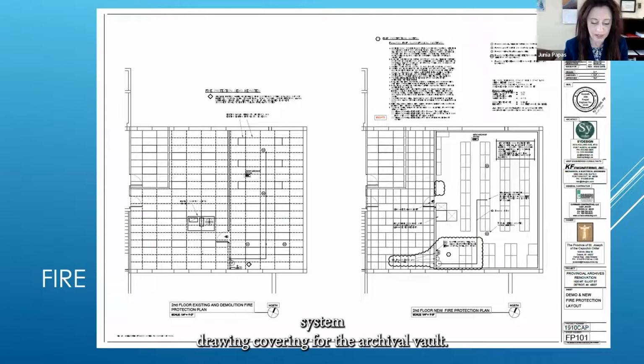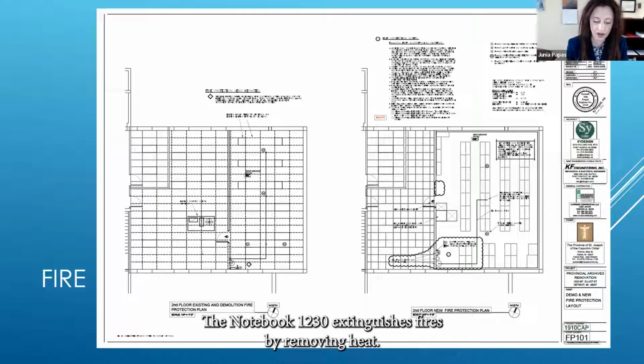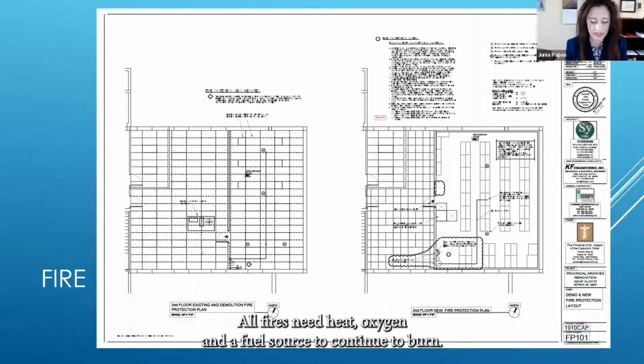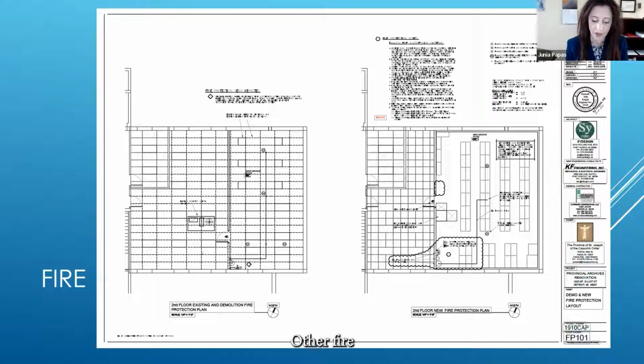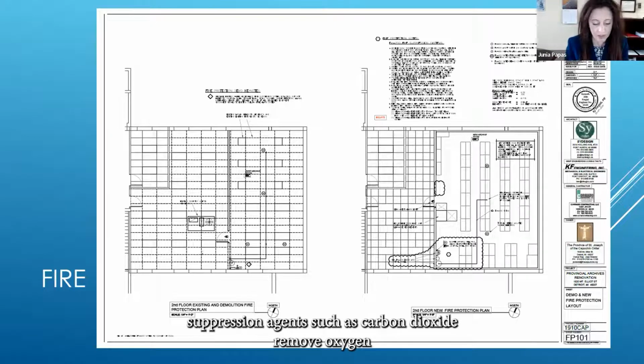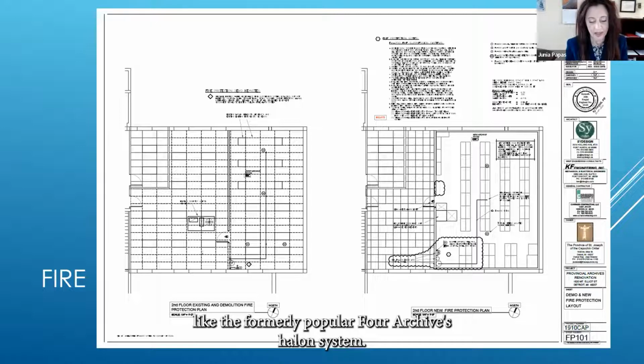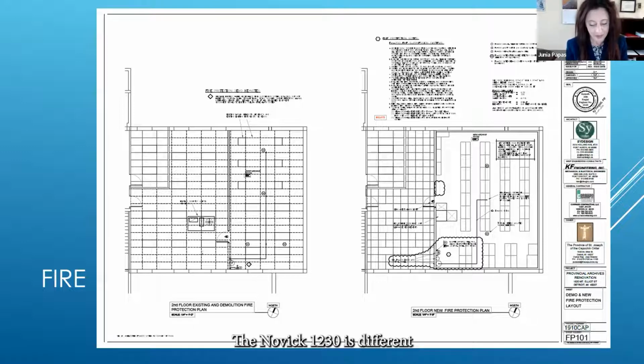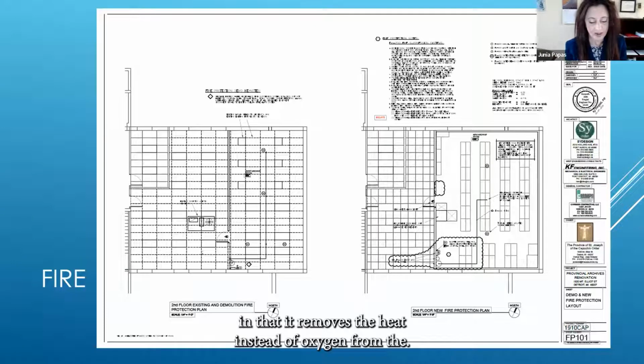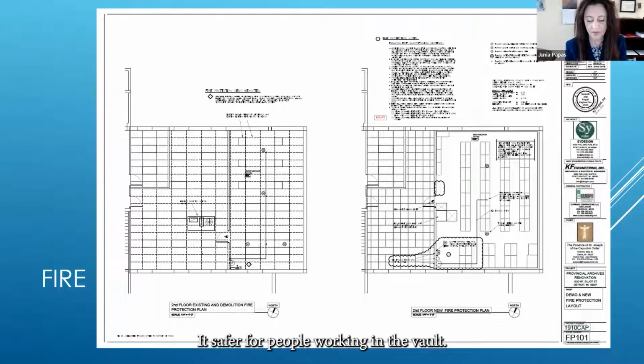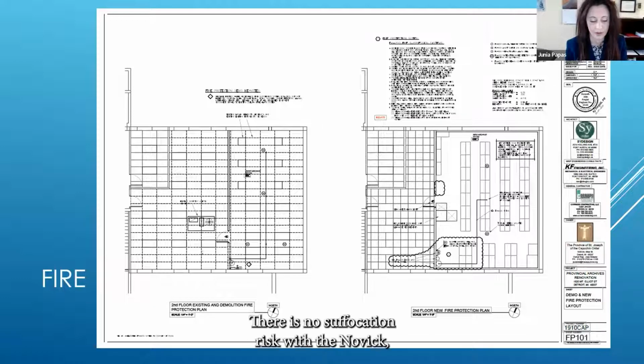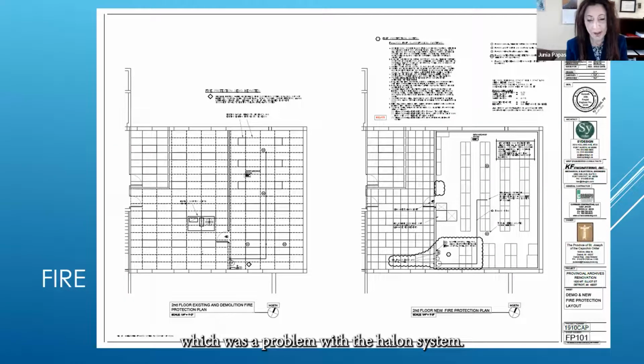This is our fire suppression system drawing covering the archival vault. The Novec 1230 extinguishes fires by removing heat. All fires need heat, oxygen, and a fuel source to continue to burn. By removing any of these 3 elements, a fire will go out. Other fire suppression agents, such as carbon dioxide, remove oxygen, like the halon system, formerly popular for archives. The Novec 1230 is different in that it removes the heat instead of oxygen from the fire, thereby making it safer for people working in the vault. There is no suffocation risk with the Novec, which was a problem with the halon system.